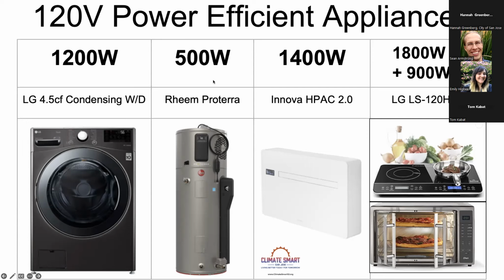Then here I have this. This is a heat pump water heater that doesn't have electric resistance backup. So instead of being 4,500 watts and 240 volt, this is 500 watts and 120 volt. And you can plug it in anywhere. And this provides just as much hot water in the first hour, which is like 72 to 80 gallons. And the water is essentially stored like a little battery. It's stored hotter at 140 degrees Fahrenheit and then delivered at 120. That's what this black extra thing here is for, is mixing the water down to 120.